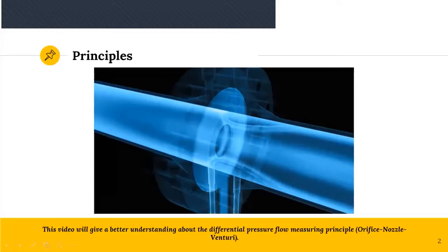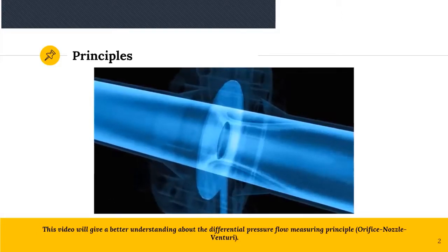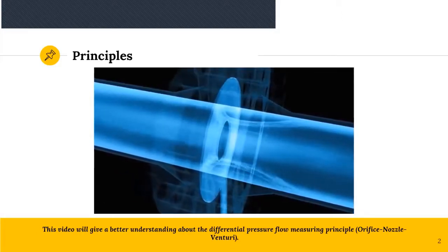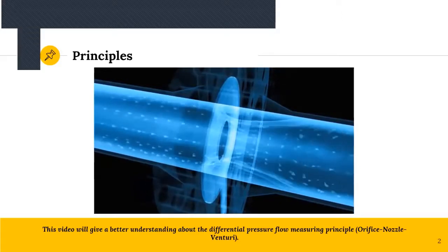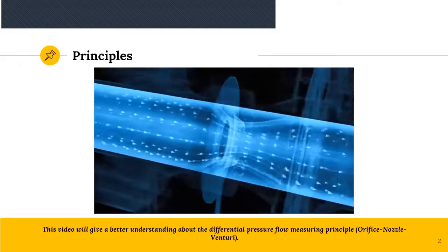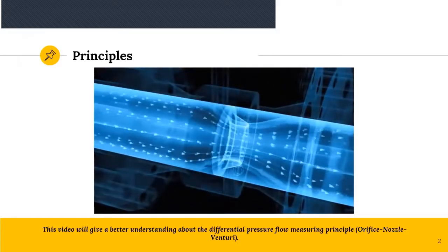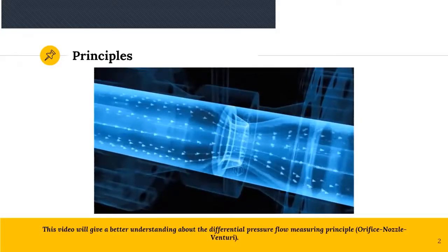In numerous industrial applications, the orifice plate covers many needs of flow measurement technology. However, other designs are available for certain measuring tasks to minimize undesired effects, such as excessive pressure loss or abrasion of components due to solids carried in the fluid. This demonstration shows that an abrupt restriction generates severe turbulence in a fluid. Nozzles with a rounded, funnel-like inlet clearly reduce turbulence and thus create less pressure loss.